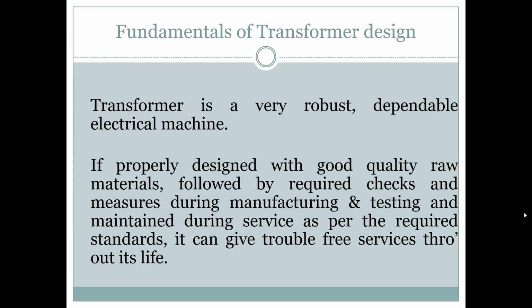Out of all the machines, I must say the transformer is the most robust, dependable electrical machine. If properly designed with good quality raw materials, followed by required checks and measures during manufacturing and testing, and maintained during service as per the required standards, it can give a trouble-free life throughout its life. I have seen transformers which have not given any trouble during 25 years of life. That is the average, but still, Russian transformers are working past 40 years. But there is one interesting subject here. There is a joke in the international market of CRGO.